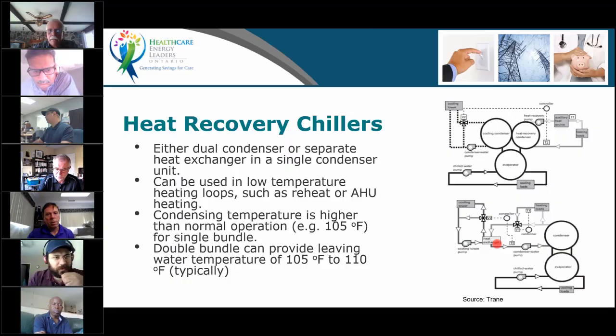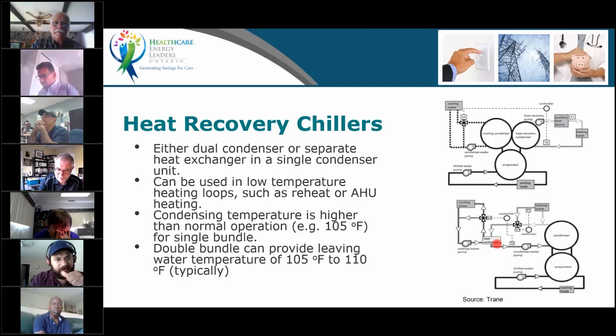I just have a quick question. Can you put a little bit of light on cogeneration? We have a cogeneration plant here at the Hamilton General Hospital, and do you think it's a good idea to use heat recovery chillers when we have a cogeneration, because we are generating our own electricity and we have a low temp and a high temp, but at the same time we have cooling towers that are dedicated just for the chillers? So do you think it could be a good idea to use cogeneration and a heat recovery chiller together?